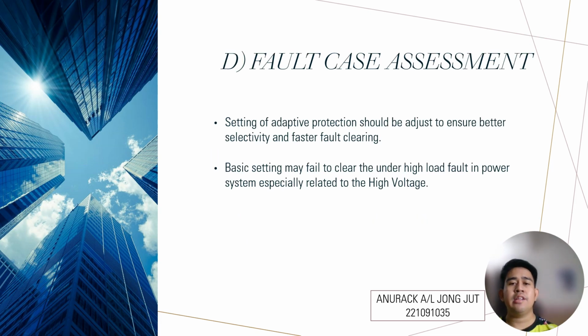Okay, next will be fault case assessment. So what is fault case assessment? Fault case assessment is the setting of adaptive protection that should be adjusted to ensure better selectivity and faster fault clearance, so it won't delay the system operation. Next, the basic settings may fail to clear faults under high load in the power system, especially those related to high voltage.